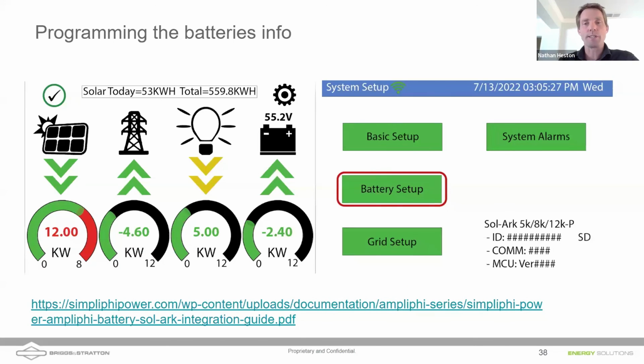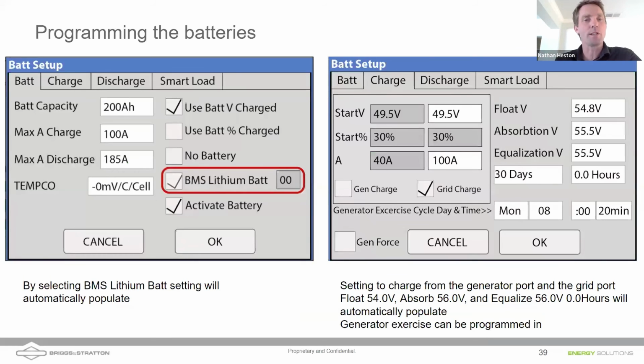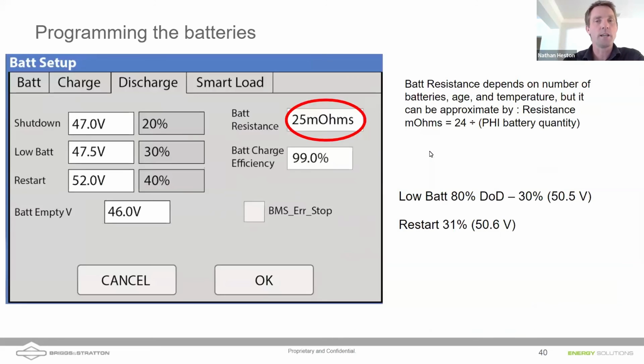When you are doing battery setup, it's relatively easy, because if you have a communicating battery, like the Briggs & Stratton SimpliPhi batteries, you can simply check that BMS box there, and almost all of the settings are going to be auto-populated for you. Now, you do need to choose what options you want in order to set for charging. So you can have a generator do charging. You can have the batteries charge off grid. You might want to only limit your batteries to charging off of solar, and so you wouldn't check either of those if that's the case.